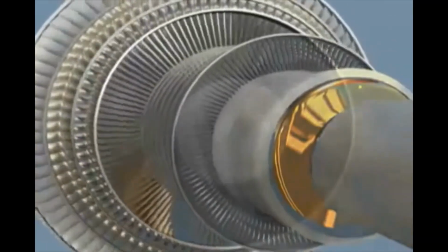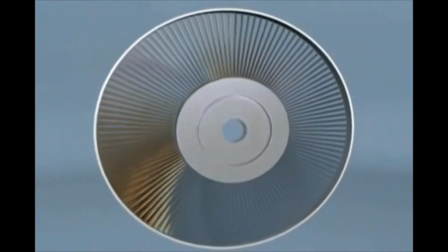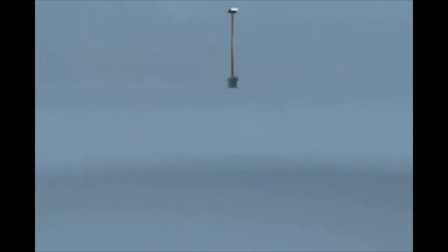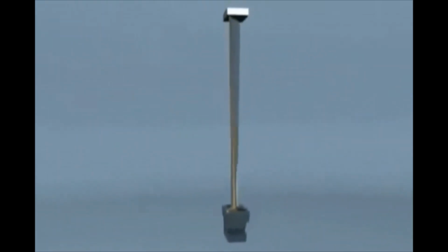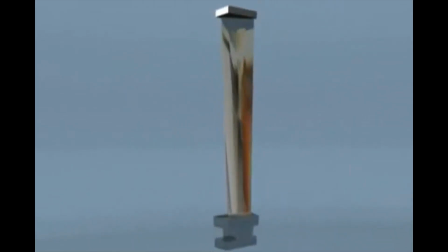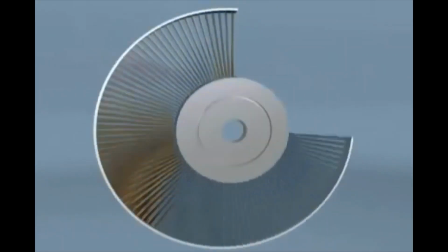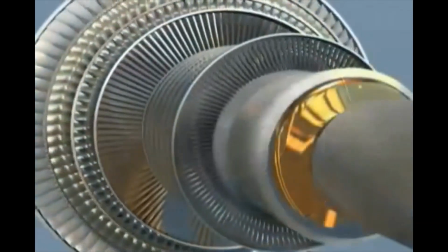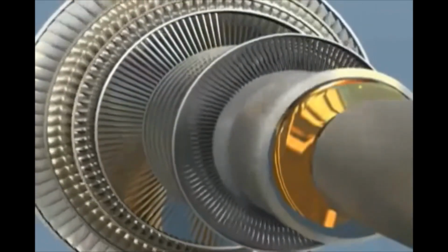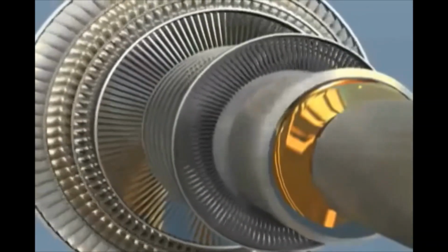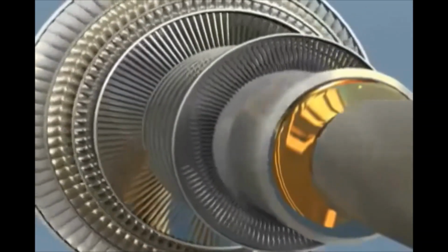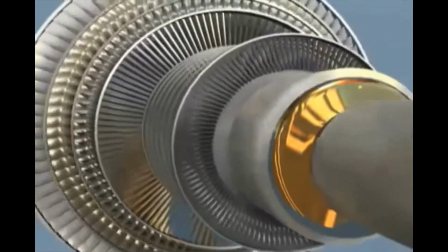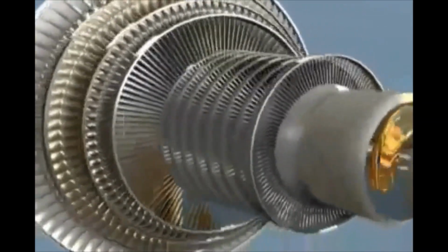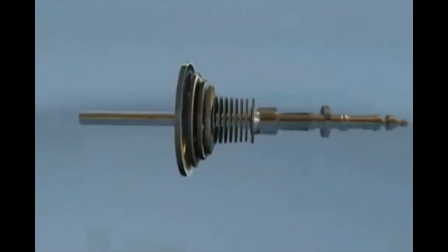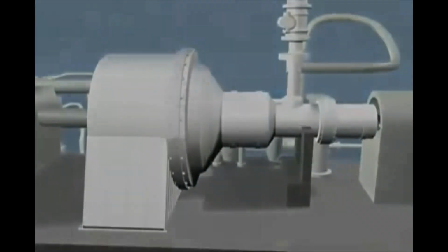The rotor blades are removed and then reverse engineered utilizing a coordinate measuring machine and the latest design software. The new blading is manufactured with state-of-the-art CNC milling machines and subjected to final dimensional and non-destructive testing. The new blading is installed in the rotor, final inspections are performed, and the complete assembly is balanced in an operating speed balance facility to guarantee smooth, reliable operation. Thank you.